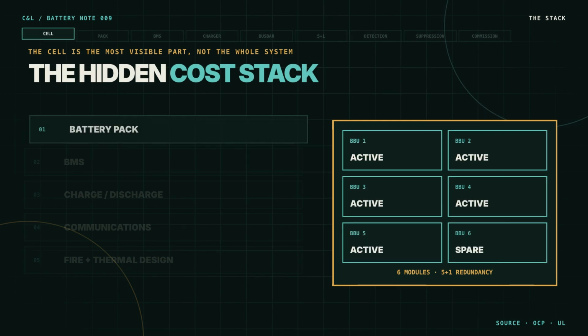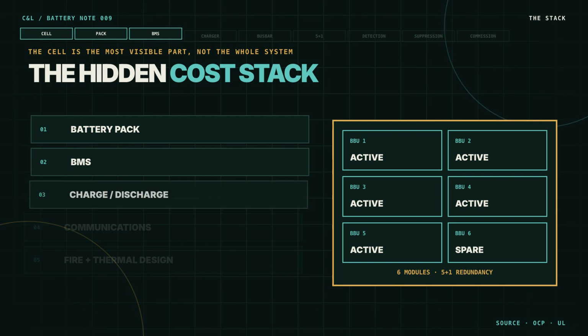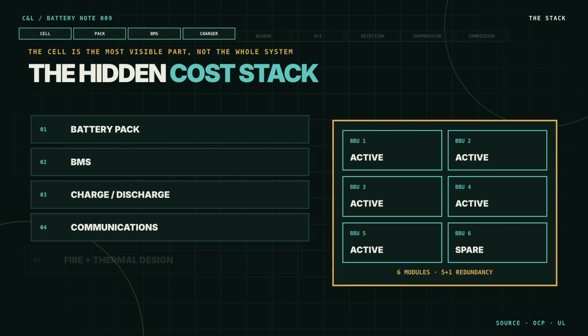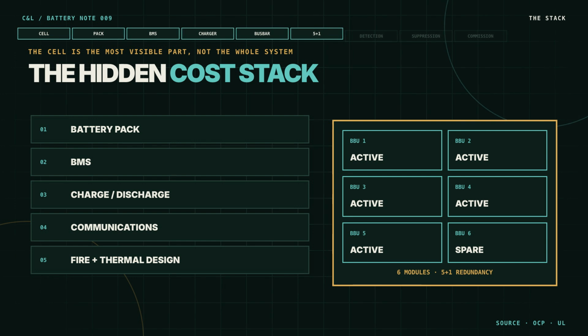Open a modern rack battery module and the cost stack becomes visible. The Open Rack specification describes a battery pack, a battery management system, a charger and discharger, communications, health monitoring, and other functional blocks. The shelf holds 6 modules in a 5+1 redundant arrangement. That spare unit is not wasted inventory. It is the price of surviving one module failure without losing the protected load. Move from the rack to a central or site-level system, and the surrounding equipment expands. Rectifiers, inverters, busbars, breakers, switchgear, controls, ventilation, detection, suppression, enclosures, and commissioning tests.